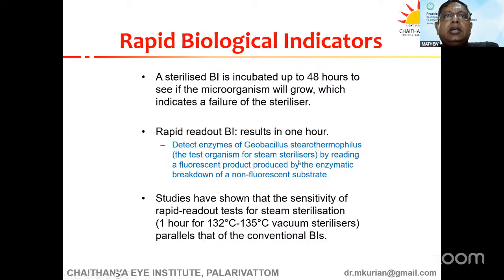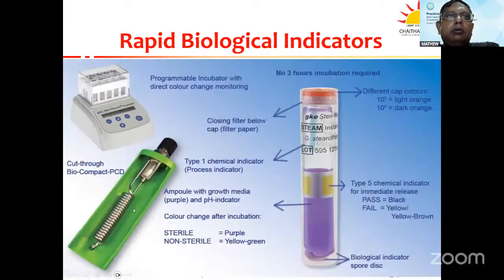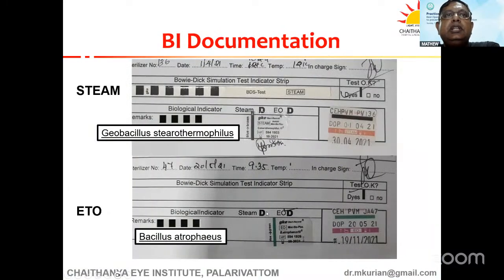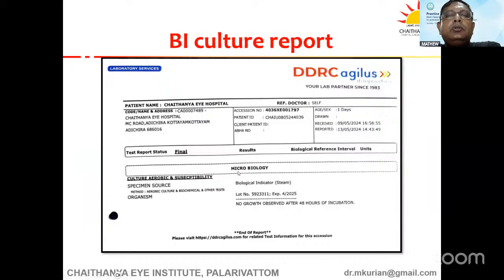So rapid biological indicators are available, which are equivalent to the full cultured report. Ideally, what you should do is load this inside the process challenge device, the change of color will indicate that this rapid report is acceptable, but the solution at the bottom of the tube needs to go into the incubator, and at the end of incubation, we need to ideally get a report which will say that there was no culture. And this is again documented, biological indicator, what was the change in color, the batch details, process device, that is for both steam and ETO are kept like this. The biological indicator is Geobacillus stearothermophilus for steam and Bacillus atrophaeus for ETO. And the culture report is also kept, and this will show that no growth observed after 48 hours of incubation, and then we are safe to proceed.